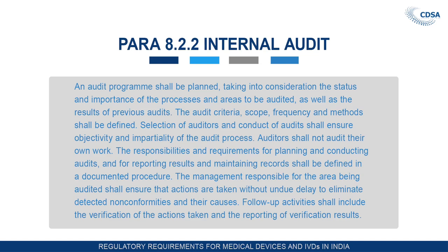The responsibilities and requirements for planning and conducting audits, and for reporting results and maintaining records, shall be defined in a documented procedure. The management responsible for the area being audited shall ensure that actions are taken without undue delay to eliminate detected non-conformities and their causes. Follow-up activities shall include the verification of the actions taken and the reporting of the verification result. After an audit, you have to prepare a non-conformity report or an audit report, in which the shortcomings are mentioned and highlighted, and a time is given for action. The deficiencies have to be conformed to the requirements within that particular time period.